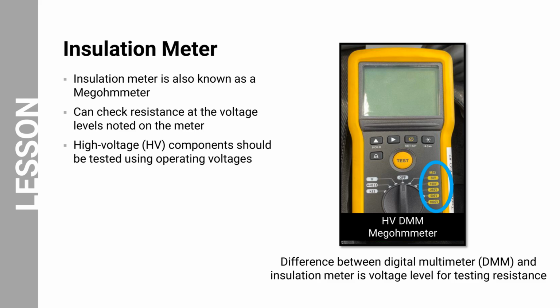On the other hand, an insulation meter provides the high voltage necessary to simulate operating conditions and effectively detect even minor insulation weaknesses that could lead to isolation faults. In essence, the high-voltage capability of an insulation meter makes it the ideal tool for isolation fault testing, allowing technicians to identify potential safety hazards and ensure the integrity of the high-voltage system.